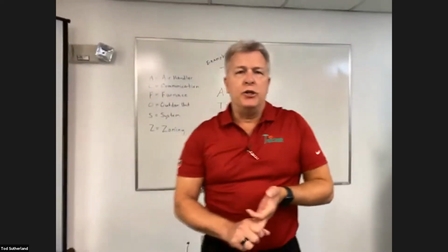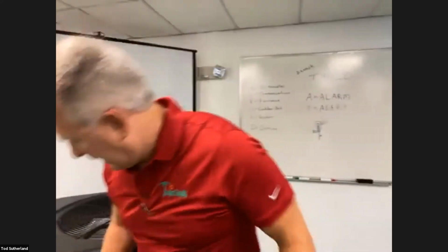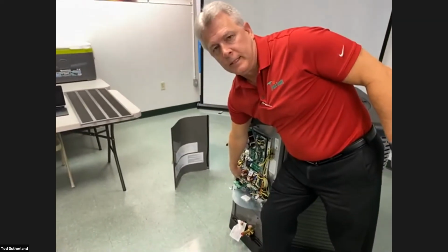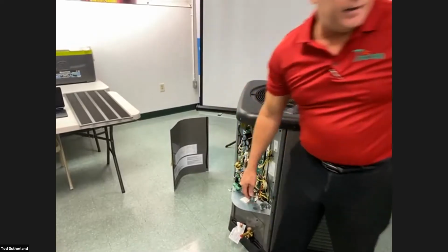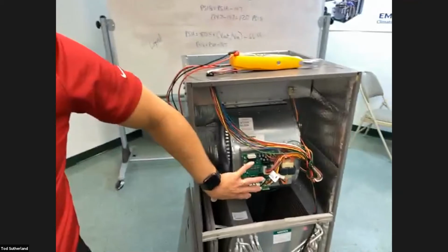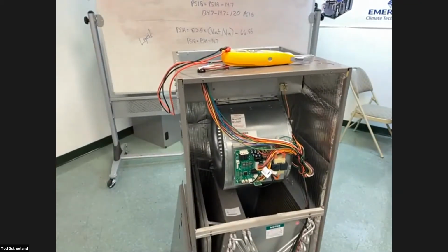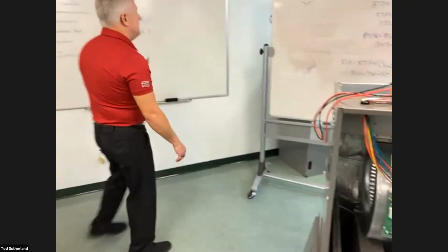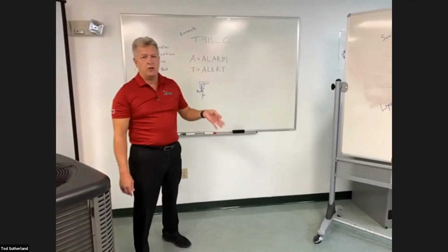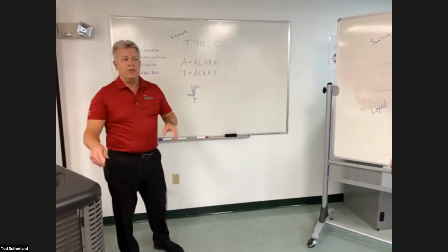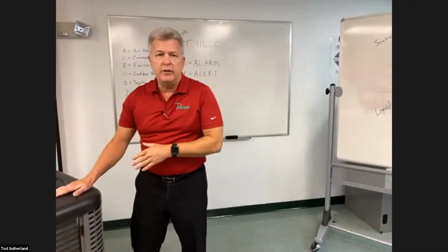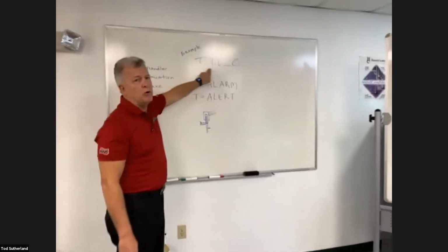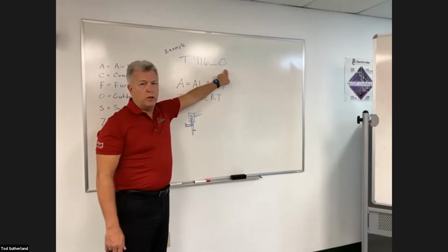There's three places that you can read error codes. You have a double-digit LED display that's on the board out here. You also have readouts on the indoor air handler with blinking lights. But I will tell you right now, the number one place to read the error codes is on the Econet controller. The condensing unit is just going to give you a 2-digit code, but the Econet controller is going to give you a much more detailed alarm or alert.